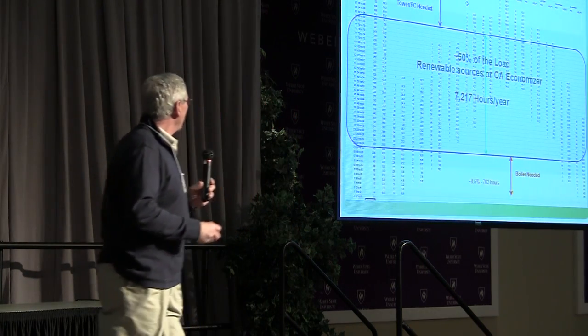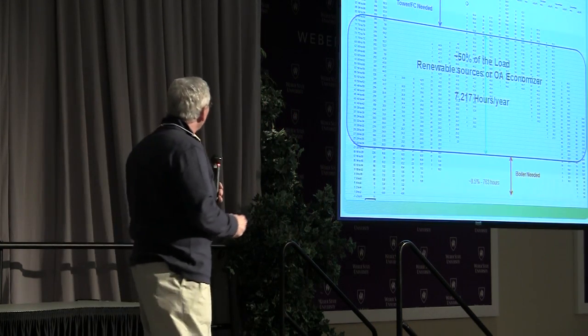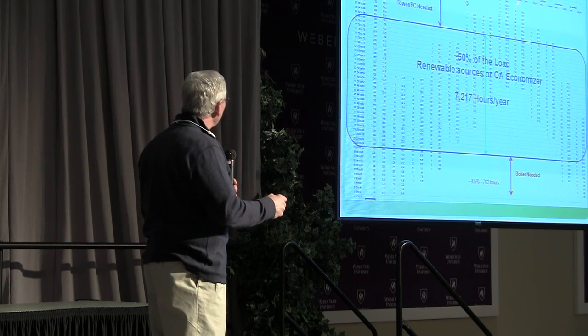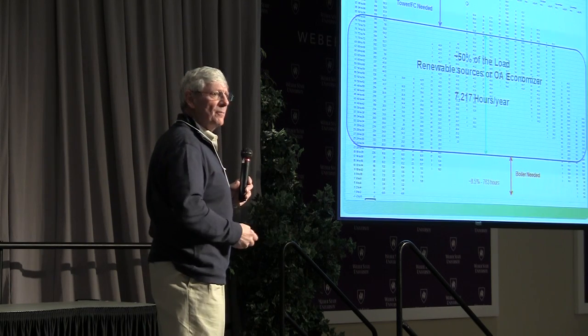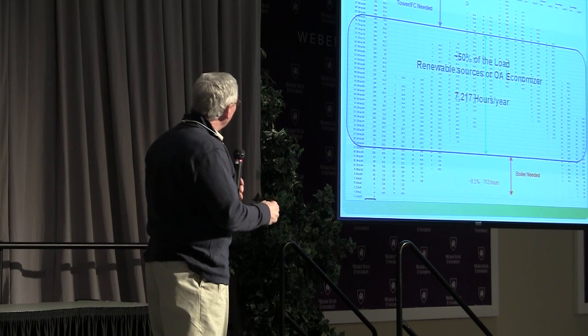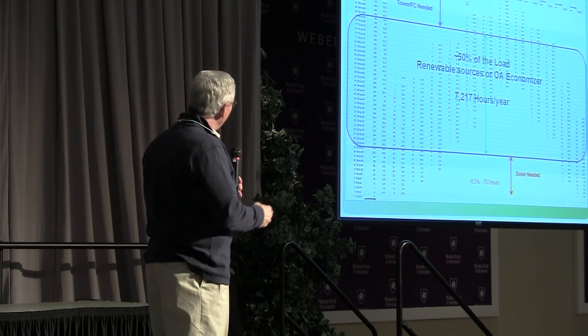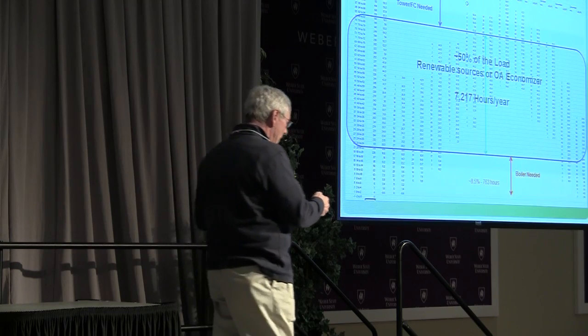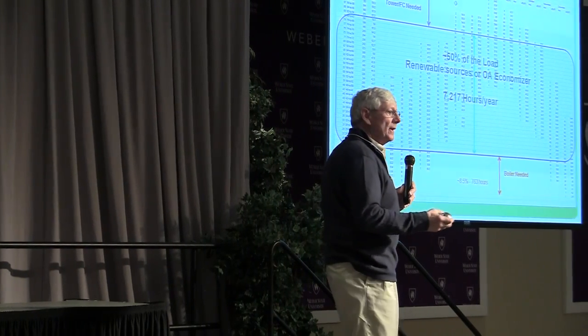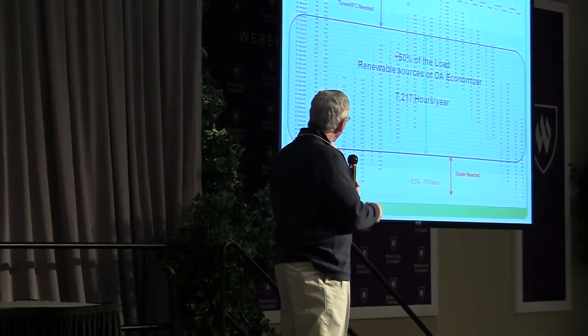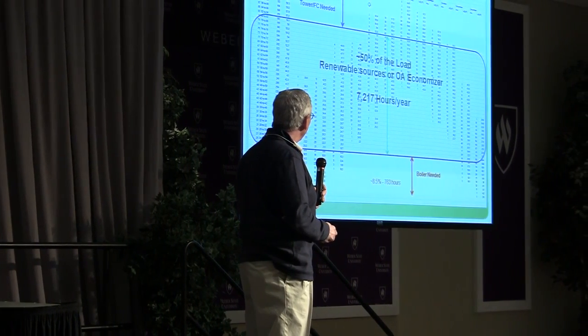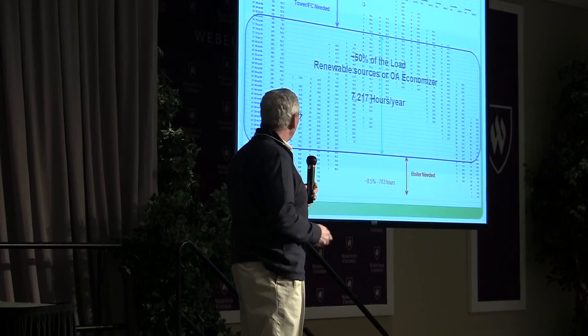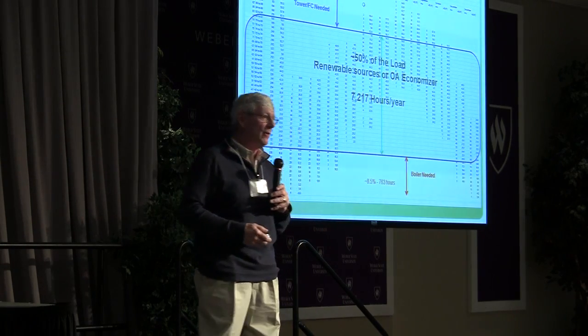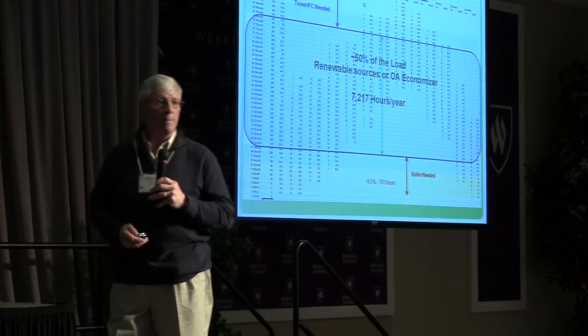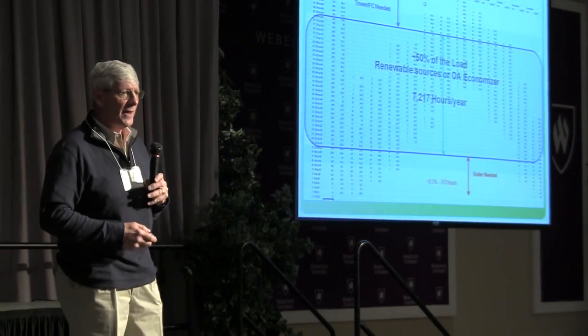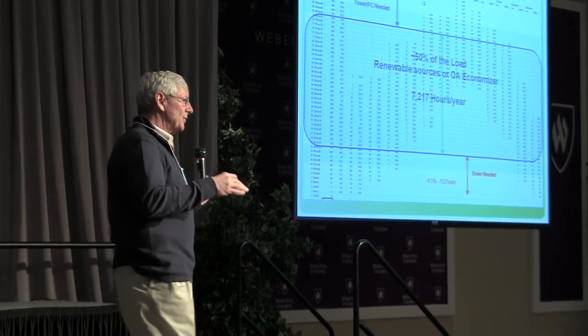This is a bin table. It's kind of neat. We have our months starting down here in the heating and going up to the middle of the year. July 17th is about our peak day here in Salt Lake City, and then we start to come down. When we look at the number of hours a year on a hybrid system, using that same formula, about 50% of the load from renewable sources or outside air economizers will handle you for about 7,217 hours a year out of 8,760. That's pretty significant. We can use the highest efficiency equipment for that portion of the year.